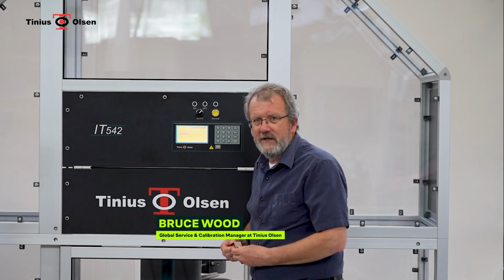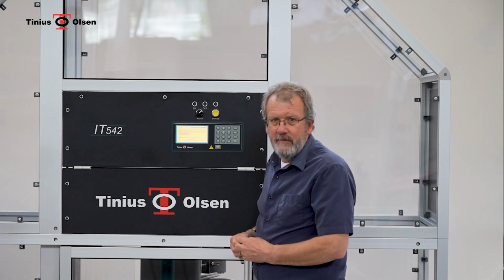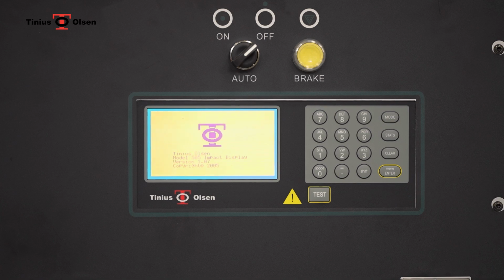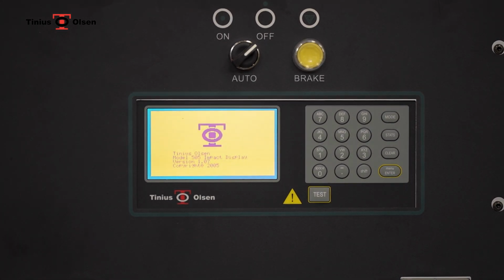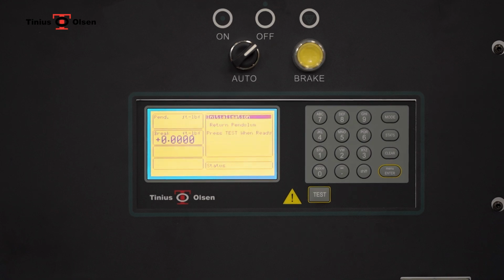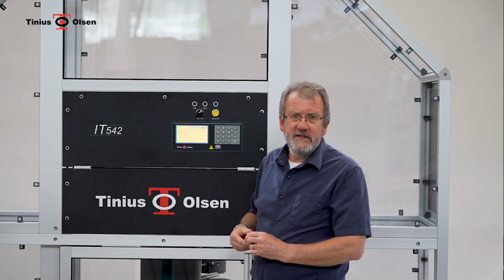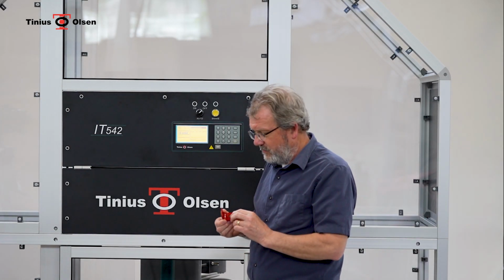Upon completion of the installation, the machine can be powered on. An initialization screen emerges, which has the firmware version and some information, and then it defaults back to the testing screen. At this point, we're ready to do a calibration, bar two things.